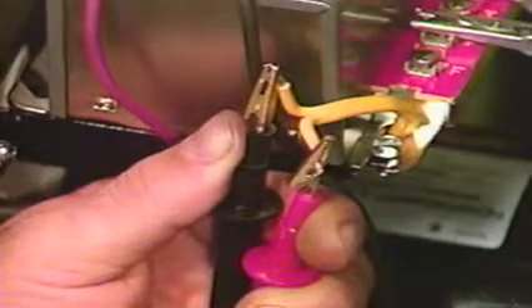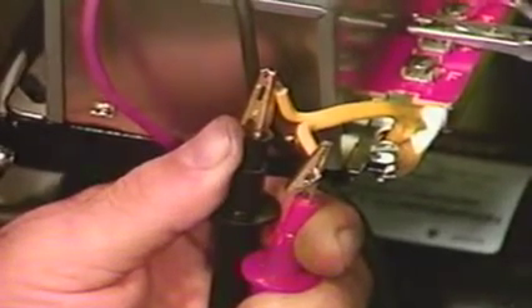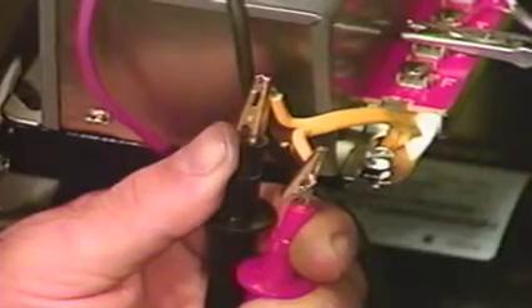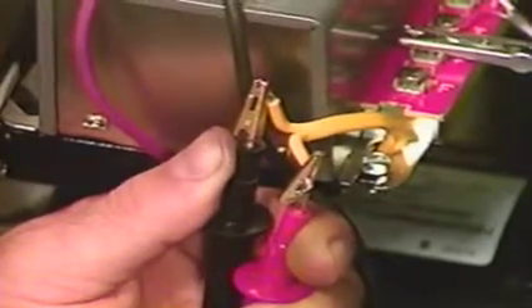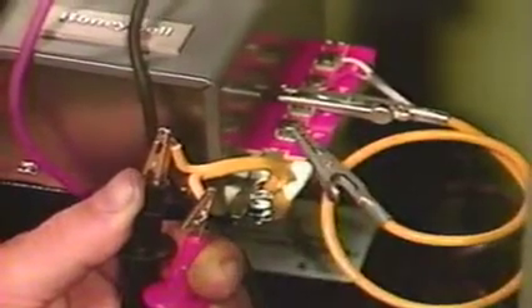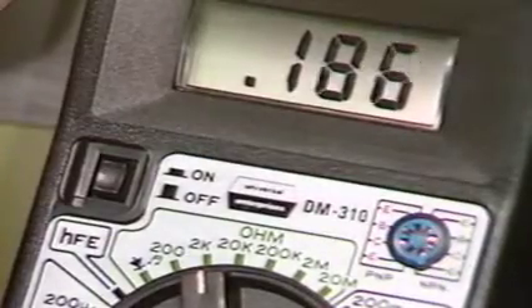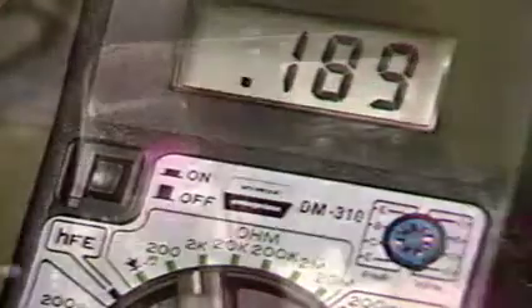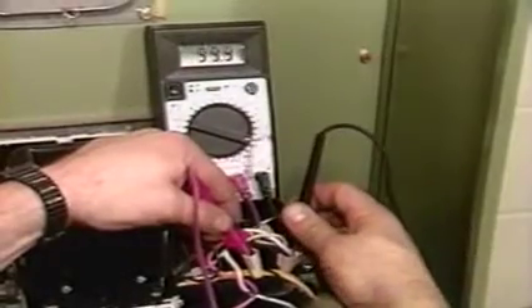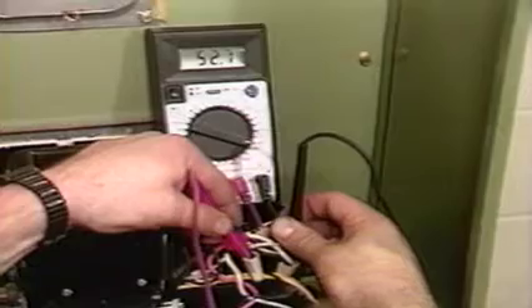To do this, remove the CAD cell leads from the control FF terminals. Attach the ohm meter leads to the CAD cell leads. Start the burner. Jumper the FF terminals. Your ohm meter reading should be less than 1600 ohms. What if the relay pulls in, but the motor fails to start? Measure voltage between the neutral lead and the primary control lead for the motor. If there's a severe voltage drop, the relay switch contacts may be defective.